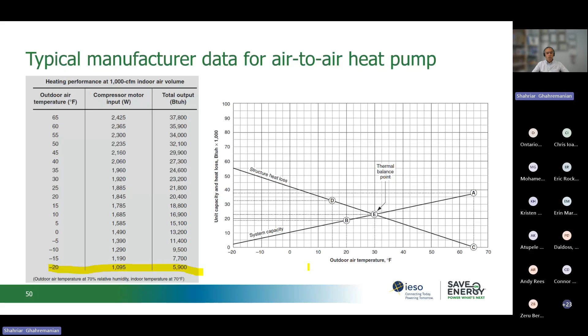On the right-hand side, we don't have any problem because that's it for cooling. And these heat pumps, usually they are sized for heating, not for cooling, because we live in a cold climate. So they have to size it based on the heating. When they size it for the heating, you will see later in the next slide that I will talk about, usually they go oversize actually. So oversize on the cooling means that we have slightly more cooling than the building actually needs. So it's oversized and it can provide a lot of cooling to our buildings.